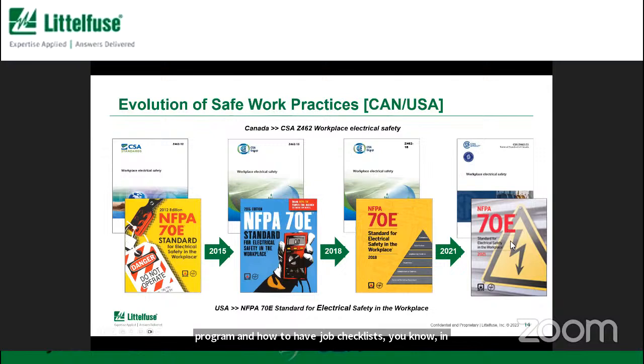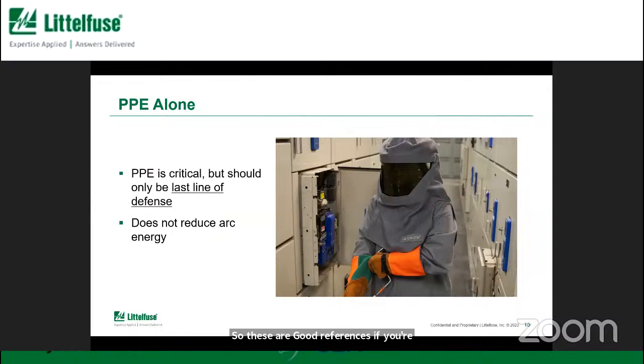So these are good references if you're interested. So if we want to look at some of the specific things to do around arc energy reduction, of course, we have PPE, personal protective equipment. And this is absolutely critical. It's very important to have the electrical workers wearing PPE that is appropriate in order to do that job. But it's really the last line of defense. We don't want to rely on this equipment, the gloves and the face shield and the suit. We don't want to rely on that as the only defense. We want to reduce the arc energy to begin with.